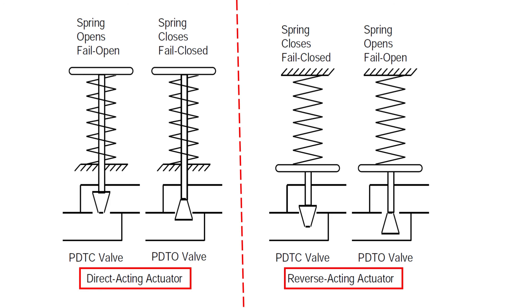This is how we achieve the fail-safe mode in both direct and reverse acting actuators. Looking at the left side — the direct acting actuator — you can clearly see the valve body. In the first figure for fail safe open, the valve plug is shown as an inverted triangle; for fail safe close, the triangle is in normal orientation. This is how the position of the valve plug and body changes to achieve the different fail-safe modes with respect to a direct acting actuator.